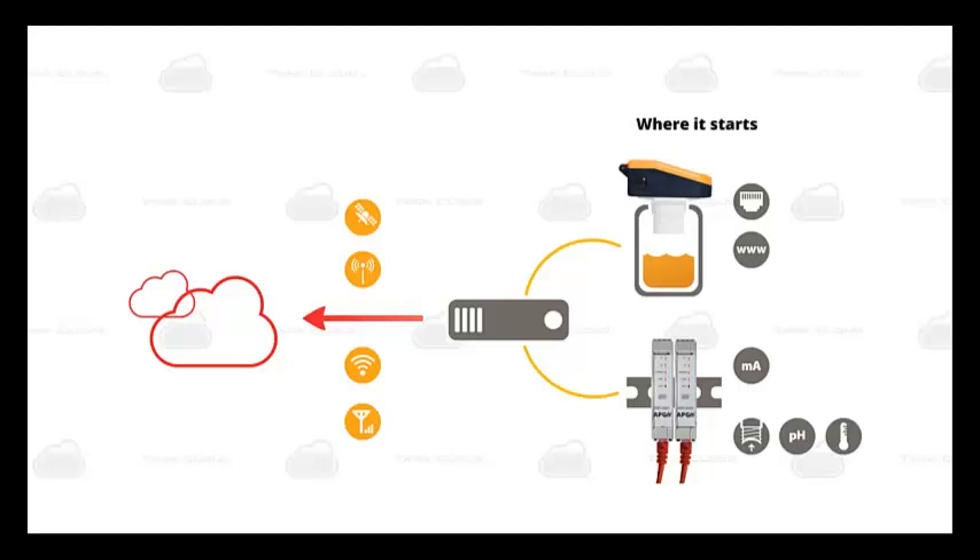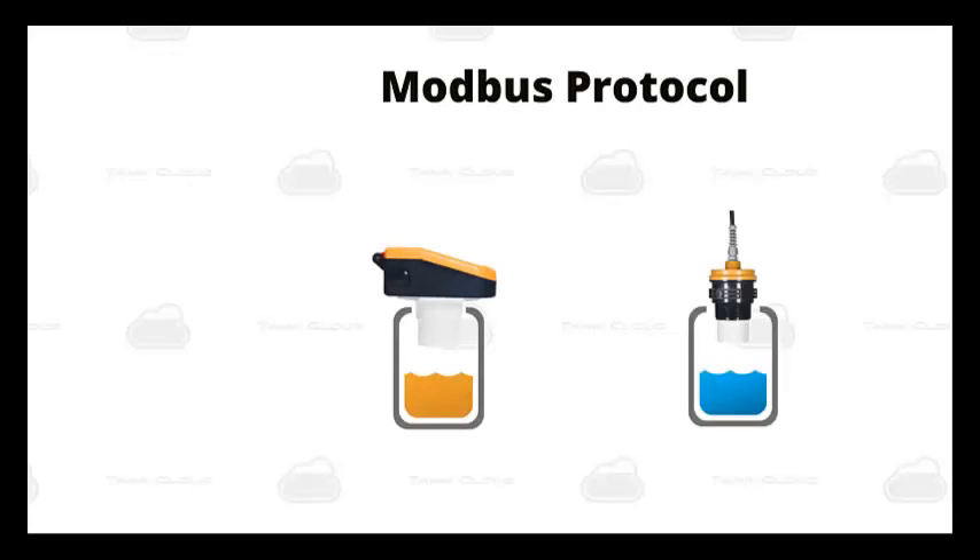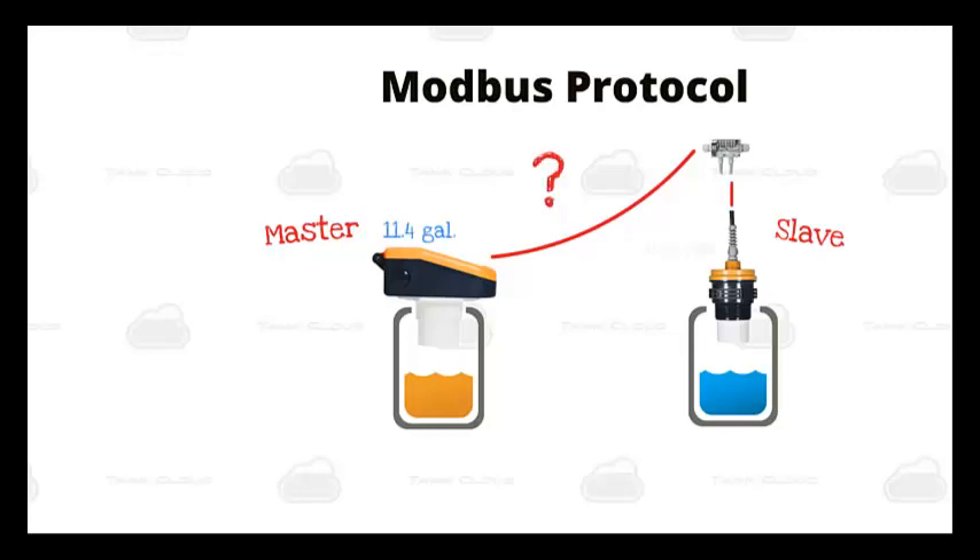Tank Cloud is now made up of several tank level sensors, modules, and displays that use Modbus protocol to send level data for many tanks to our website. If you're unfamiliar with Modbus, it's simply a communication protocol. Modbus networks have master and slave units. With Tank Cloud, the LOE is always the master unit. During a call-in from our website, the LOE will take its own reading and then polls the slave sensors for their readings. The slave units report back to the LOE, and then the LOE reports all readings to the Tank Cloud website.